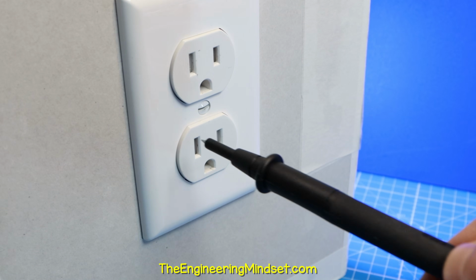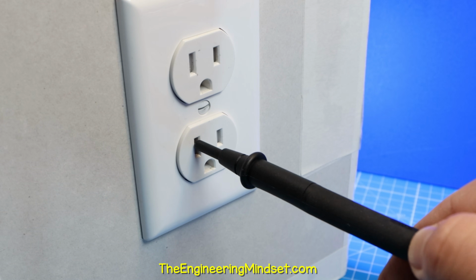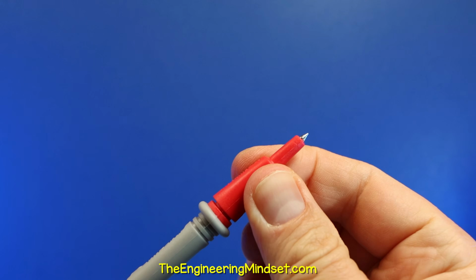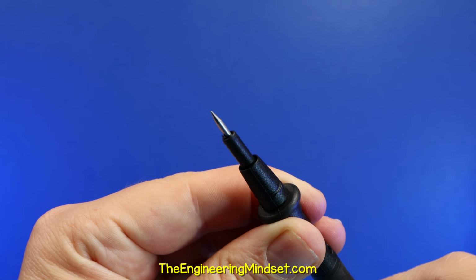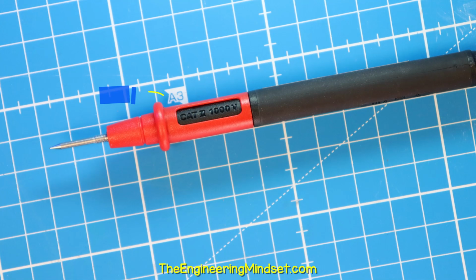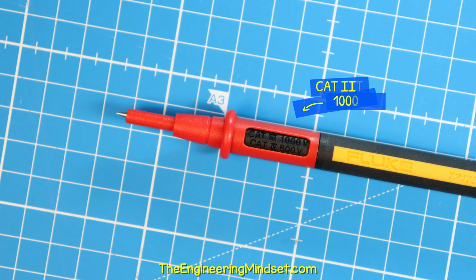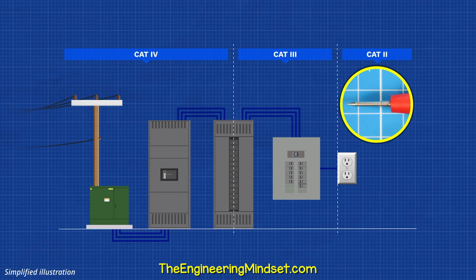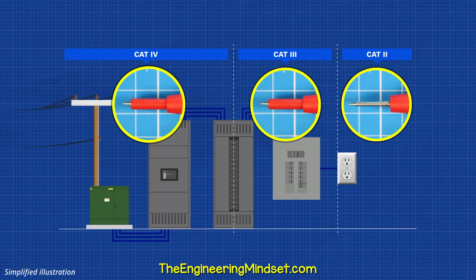If we wanted to check this outlet, our probes won't fit inside, but we can remove the end caps or twist them to expose a longer probe. However, notice that the voltage and category changes. We can only use the long probes on CAT II applications. Any higher application categories require the end caps to be placed on the tips.